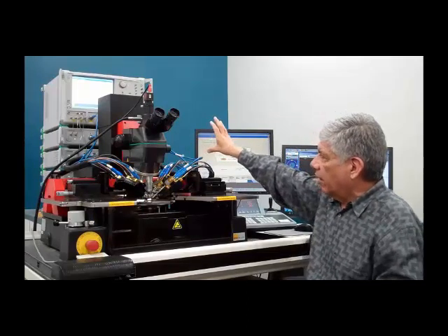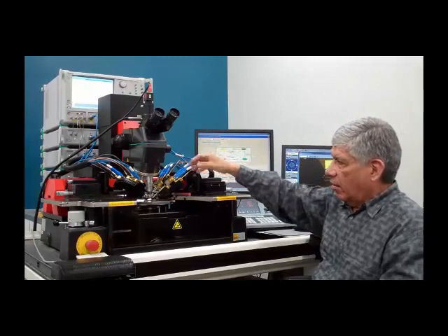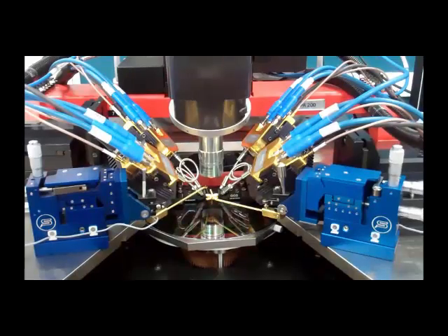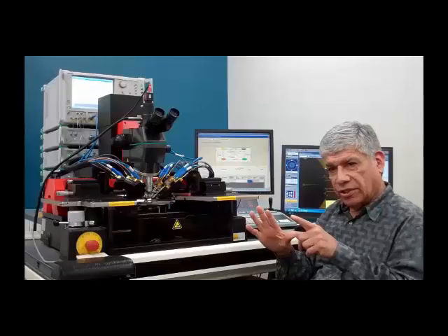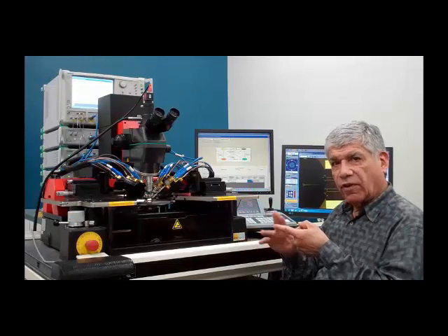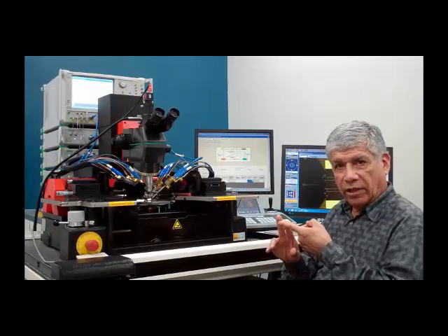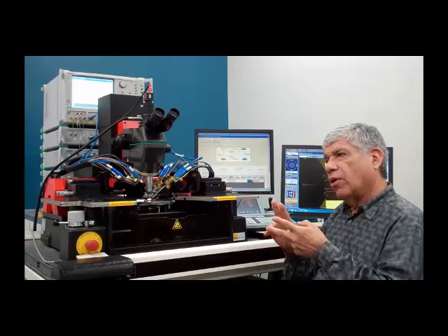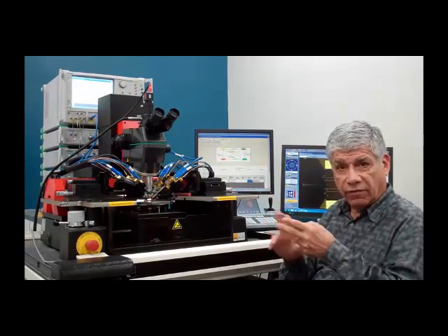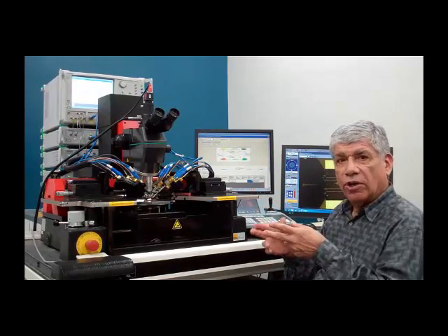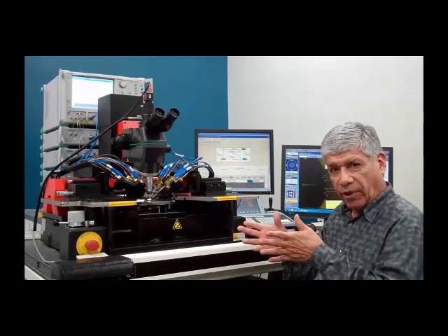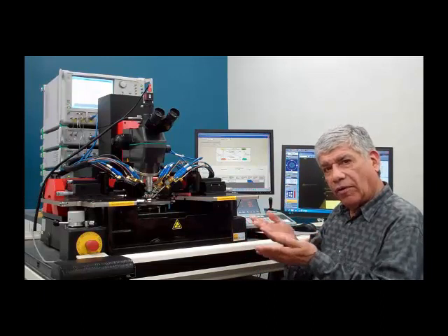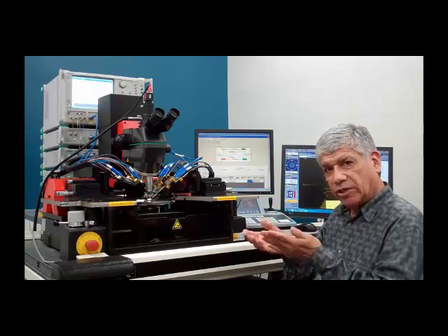So with VectorStar, in a differential setup, ports 1 and 3 can be either driven with a single source or with a dual source. Single source will give you full S parameter corrections of a 4-port device, differential devices, when they're operating in the linear region. If you're looking at nonlinear devices, differential devices, you may want to go into what we call true mode operation. And there you have control of the phase offsets between the 2 ports.